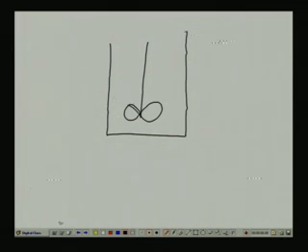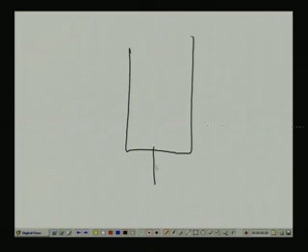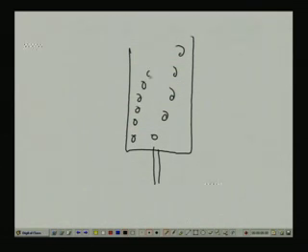In the case of bubble column reactors, what will happen? I have a vessel and I am purging oxygen through it. So, the air bubbles will go up along this path. This type of thing may cause problems in other types of dissolved oxygen probe, but that will not make a problem in this probe. Let us go back.